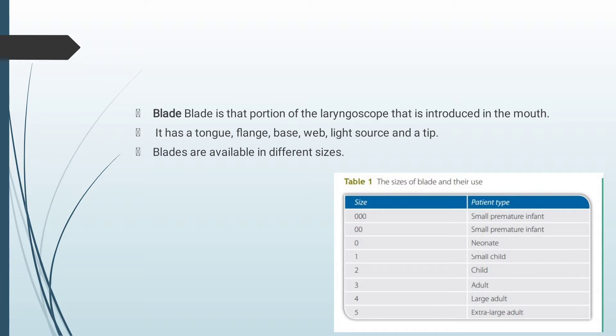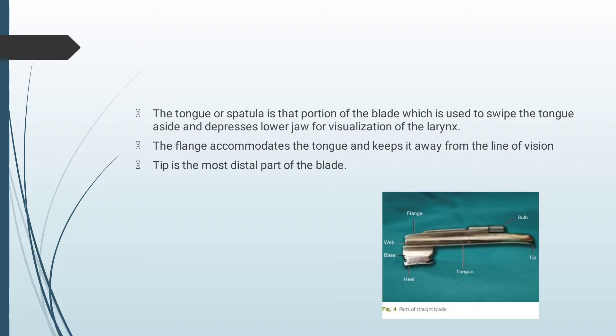The blade is the portion of the laryngoscope that is introduced into the mouth. It has a tongue, a flange, a base, a web, a light source, and the tip. Blades are available in different sizes, starting from triple zero used for a small premature infant through size 5 used for extra-large adults. The tongue or spatula swipes the tongue aside and depresses the lower jaw for visualization of the larynx. The flange keeps the tongue away from the line of vision, and the tip is the distal-most part of the blade.